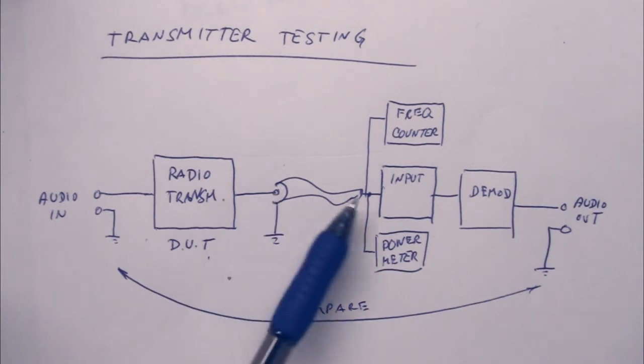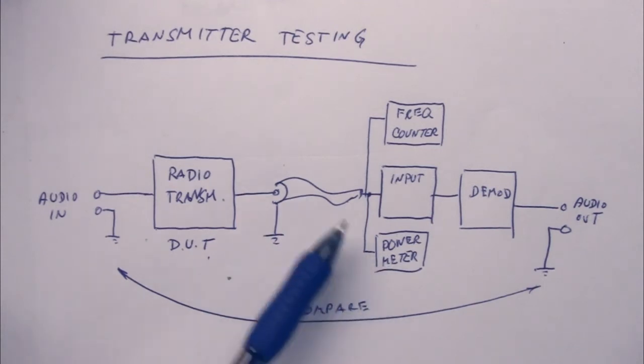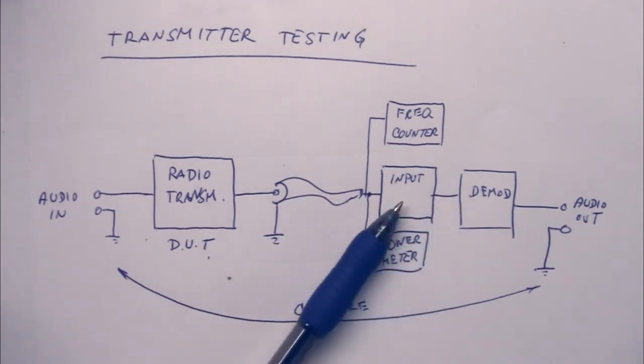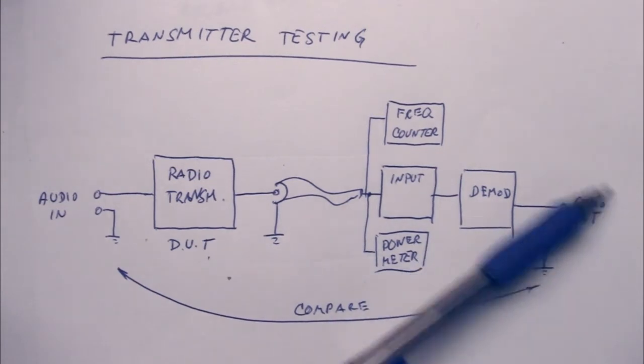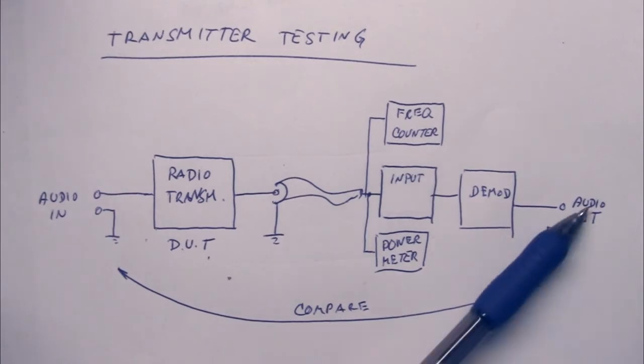And then on the antenna output, you connect all your test instruments. For example, a frequency counter, a power meter, and otherwise a demodulator. And if you have a really good demodulator, you will get your audio out, and you can do a comparison between what you send in and what you send out.